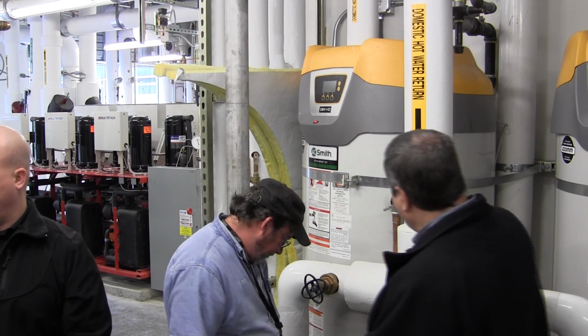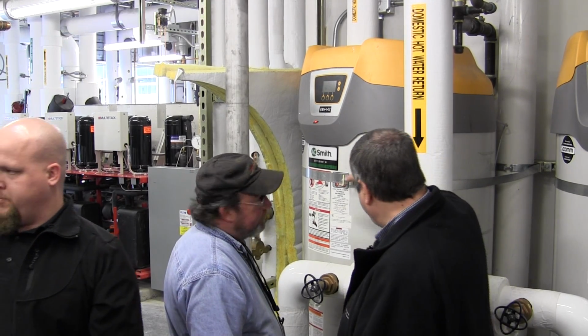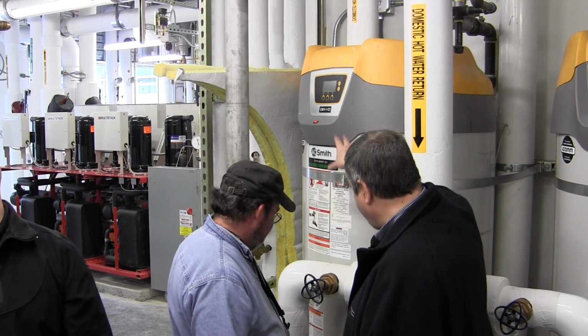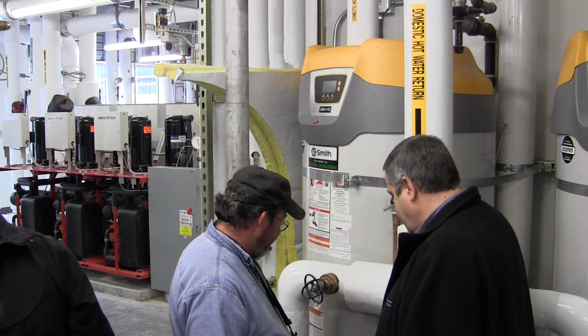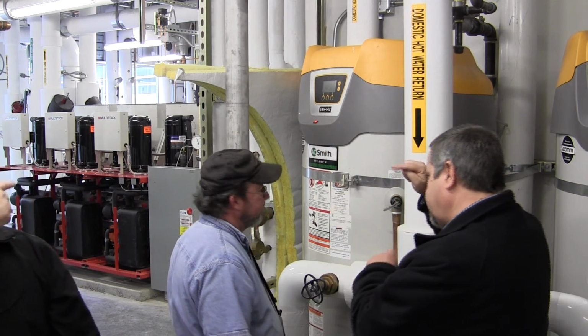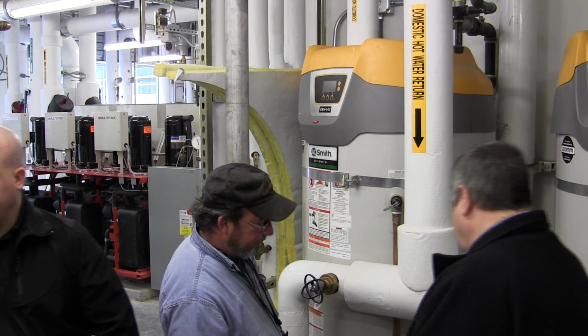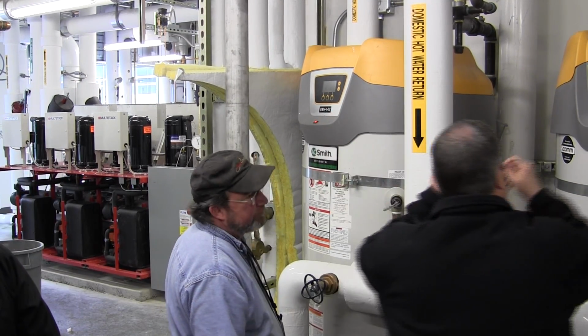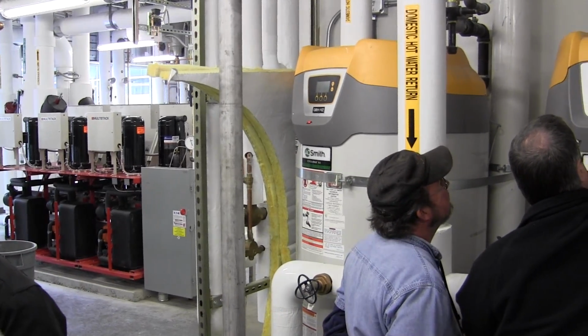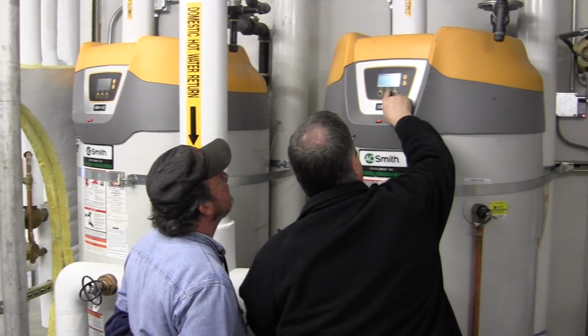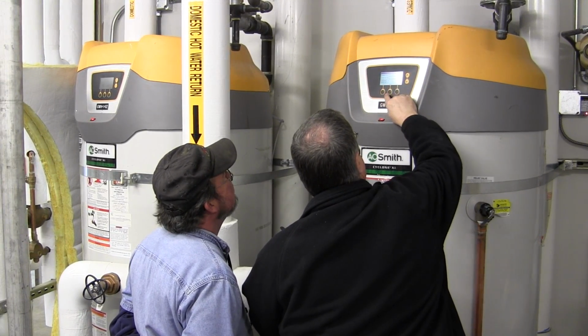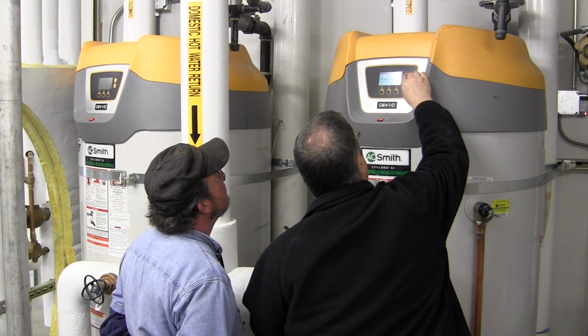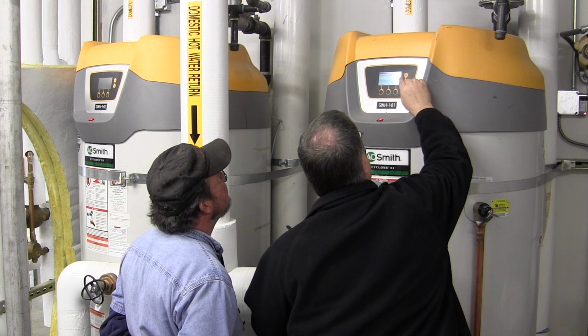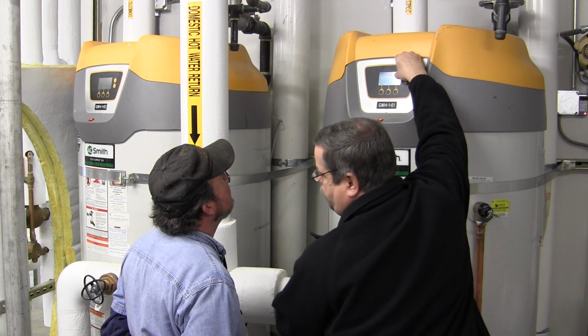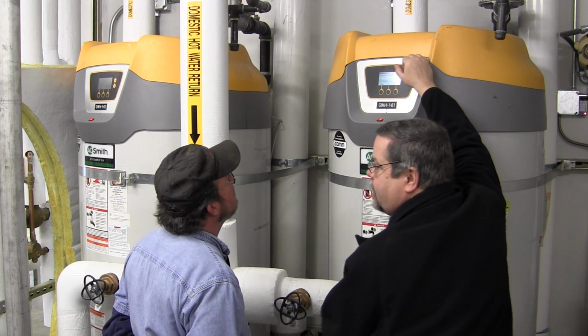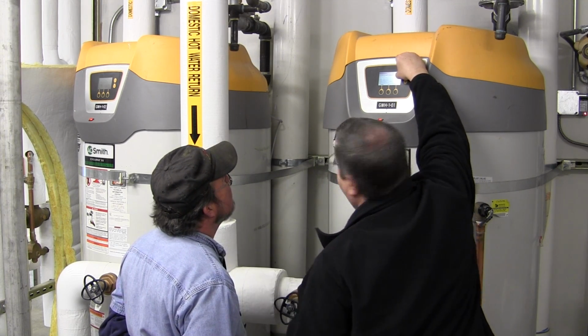Because the solar loop itself goes to the control. They sense the water in two places, on the top and the bottom, and that's how they compute how to run the heater and the temperature inside. It creates the mathematics that run the control. It needs 2 temperature points. It is just a basic temperature sensor that's sending a signal up here. If you look on here, you've got an upper temperature probe, which is 137. The lower temperature probe on this one is 129. And it takes those 2 numbers and computes the tank temperature.